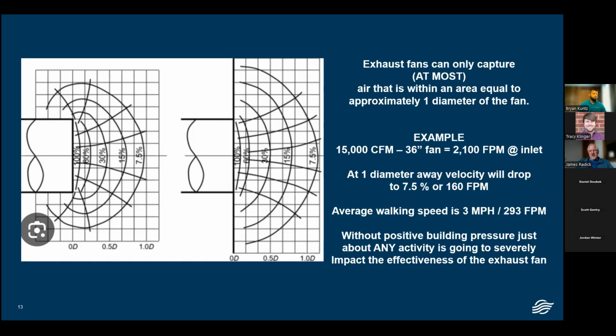If you're trying to capture dirt and nasties that are in the air, it's simply not going to happen effectively. The image on the right shows an exhaust fan, typical of a wall-mounted exhaust fan. Once you get beyond that 1 diameter away, that air is moving so slowly that, as I said in the bottom bullet point, without positive pressure just about any activity is going to severely impact the effectiveness of an exhaust fan.